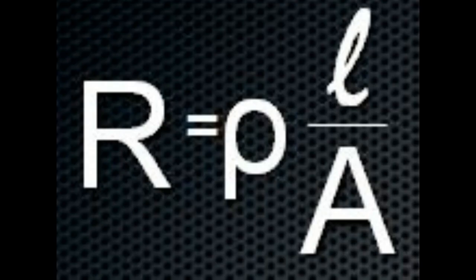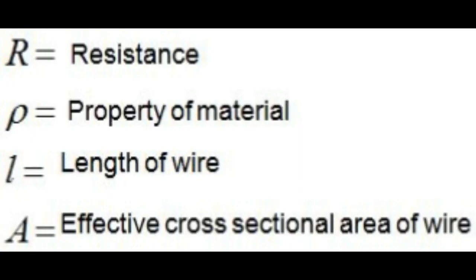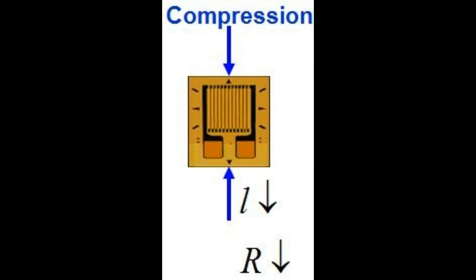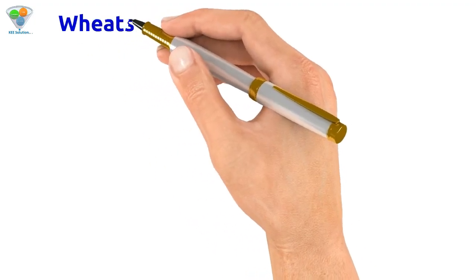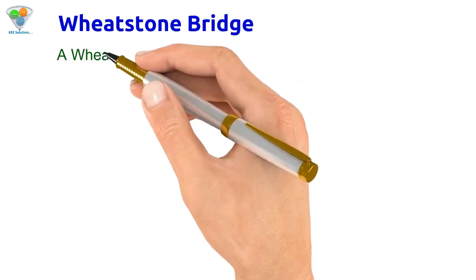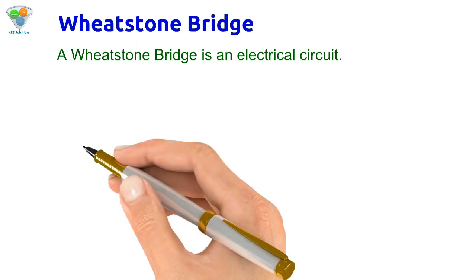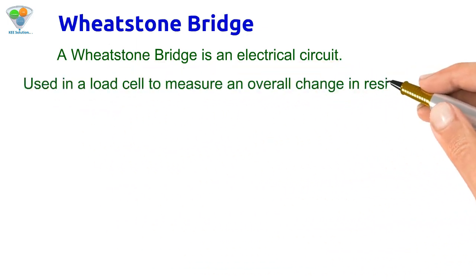When it is tensile, its length and resistance will increase. The total resistance change is commonly measured using a Wheatstone bridge. This is the basic principle of the strain gauge. A Wheatstone bridge is an electrical circuit used in a load cell to measure the overall changes in resistance.